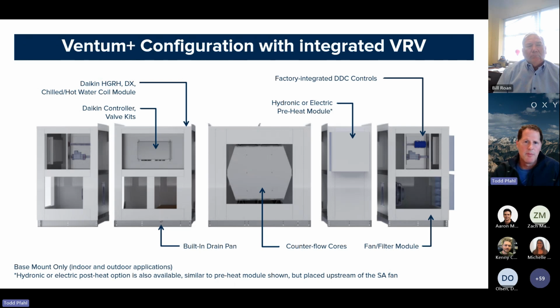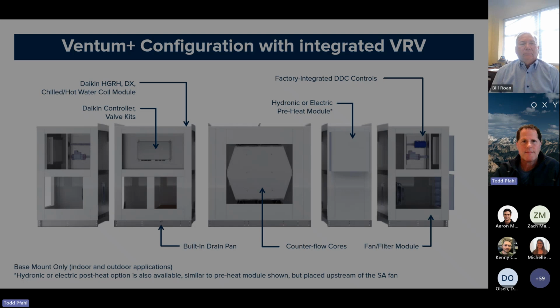We can add preheat if you need it. We can add post heating and cooling utilizing hydronic, DX, VRV systems. We can even integrate in recirculation, so we don't have to be just 100% outside air. We can recirculate and do a lot more of the comfort cooling that's required in the space. It also allows us to do some specialized filtration and even take advantage of IAQ solutions as well.